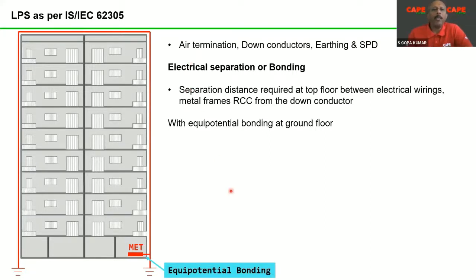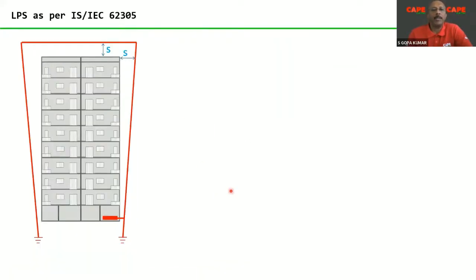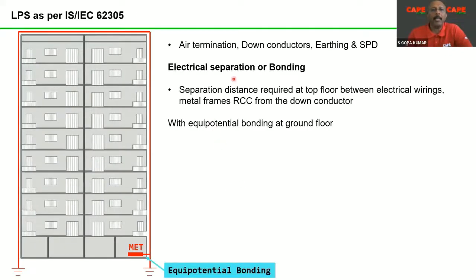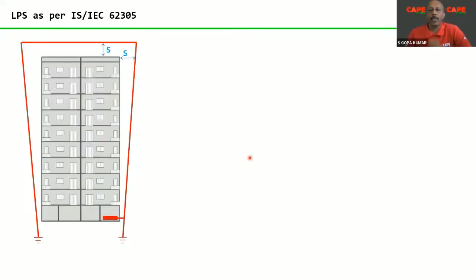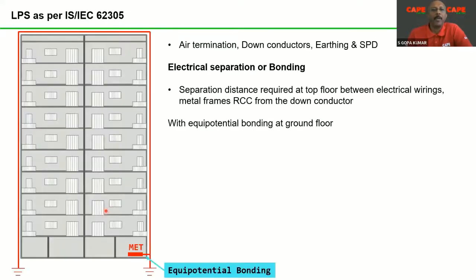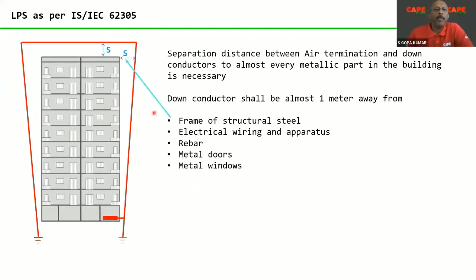Now, how to calculate the electrical separation distance? As I said, there are two techniques. One is electrical separation. The next one is bonding, which means you make equipotential bonding everywhere. First, let us look at what electrical separation is. At the roof you have the air termination, then you have the down conductor, and at the bottom of the building you have the equipotential bonding. The parts of the air termination mean the air terminal, the grid at the top, and the down conductor.